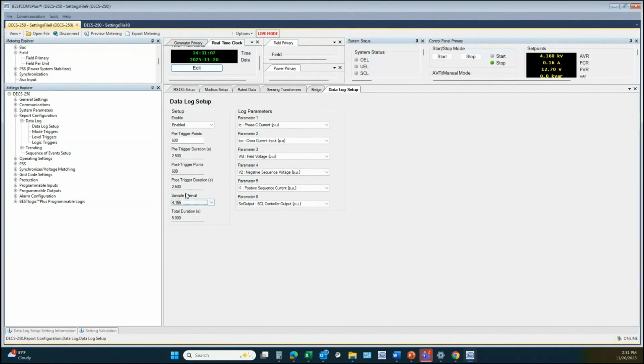And then my sample interval is the minimum, which only gives me a 5-second total recording. And I would like to have something closer to at least 20 seconds. So I'm going to increase that to at least 16 milliseconds for the sample rate, so that my total recording is about 20 seconds. I want to record the average generator voltage. I also want to see what field voltage is doing, what field current is doing, what generator frequency is doing.